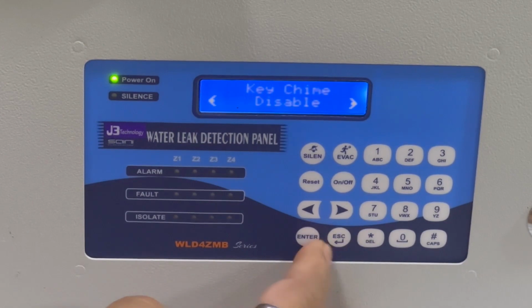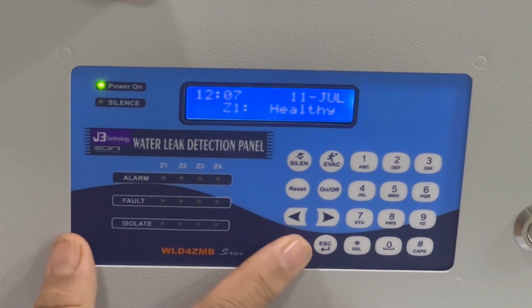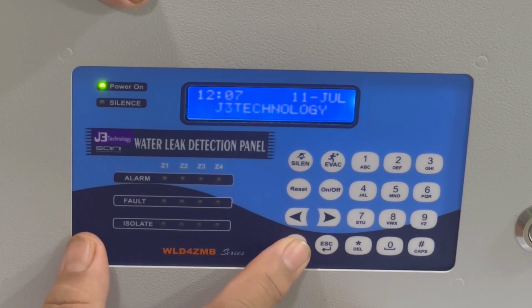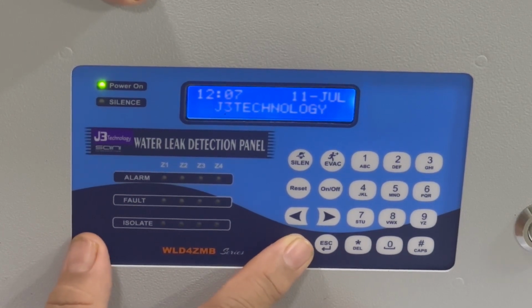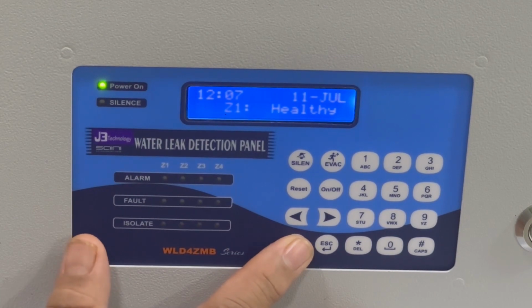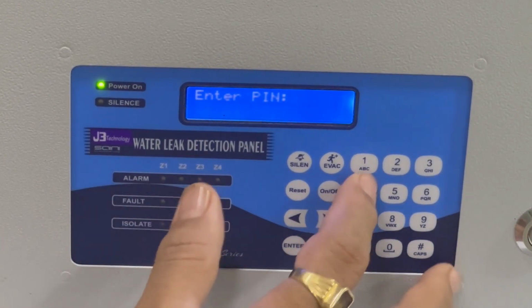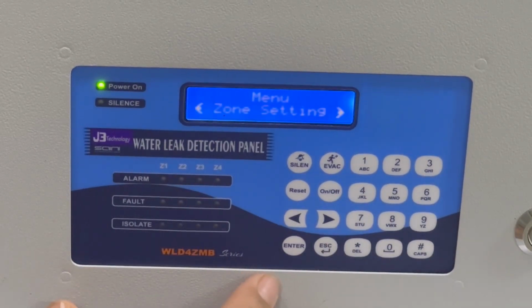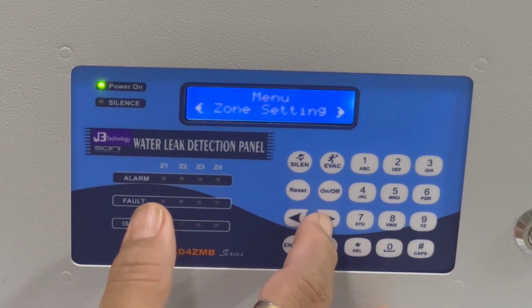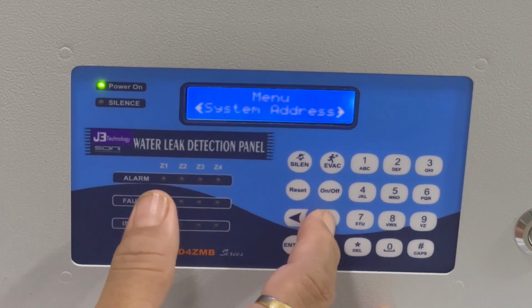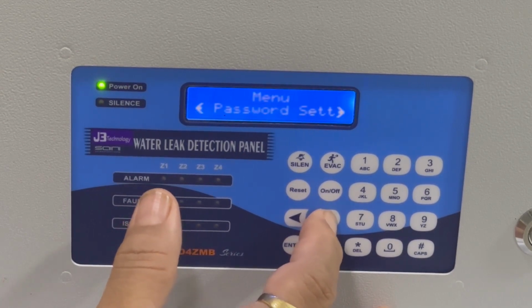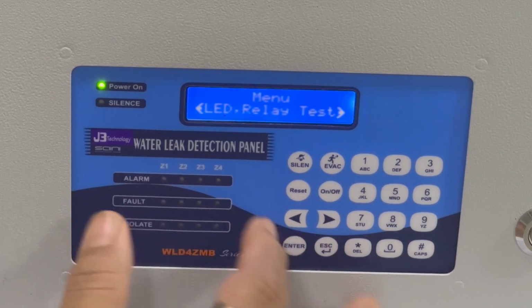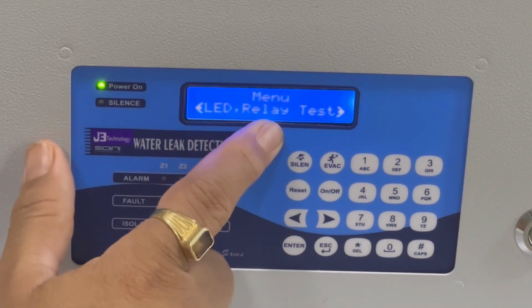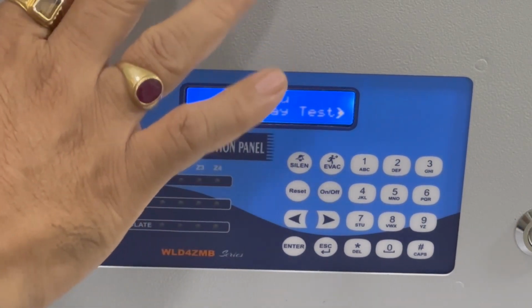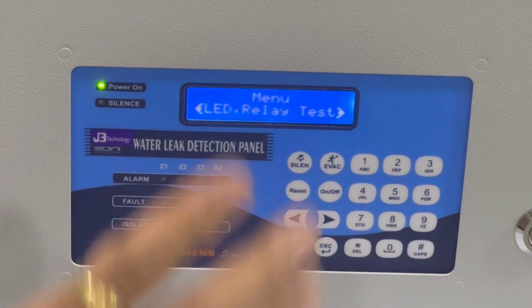Now I am showing you the other setting, that is the 12th menu setting. With it you can self-test the panel. This 12th menu has the option to self-test all the relays and the hooters. By default it is not in self-test. You have to go to the LED relay test. In this menu, the panel will automatically check whether all the relays, hooters and the fault relay are working or not. This is one type of self-test.